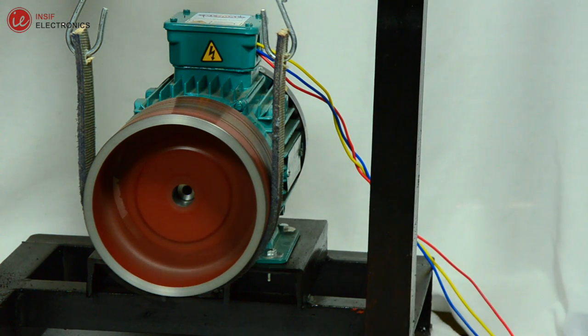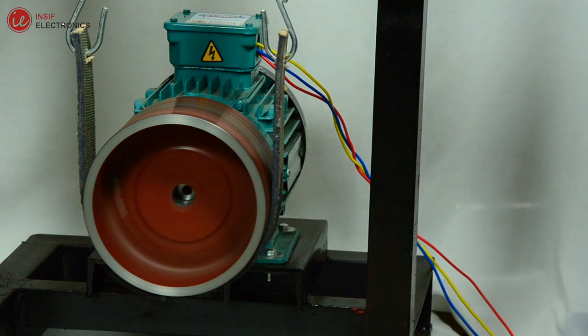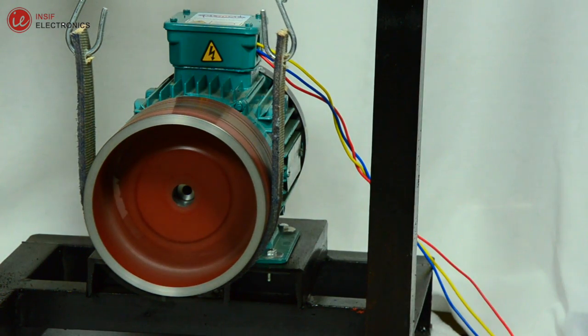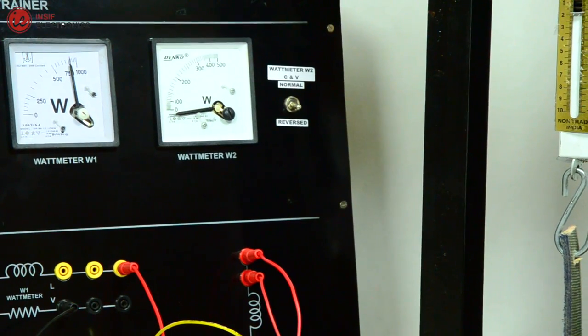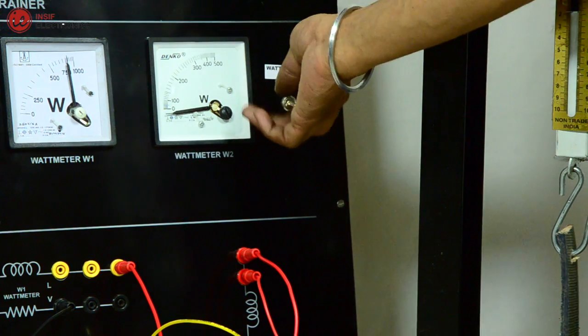As you can see, as the load is increased the speed goes down and the current increases. See the effect on different loads and make sure the current should not increase to the rated value that is 2 amperes.